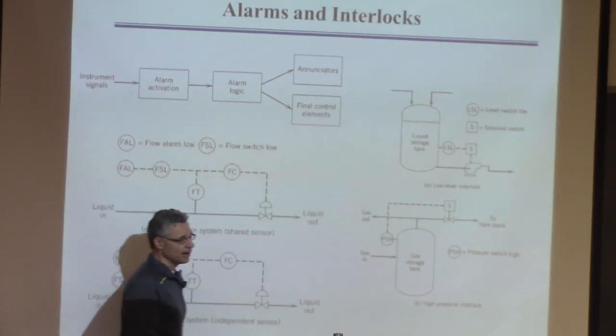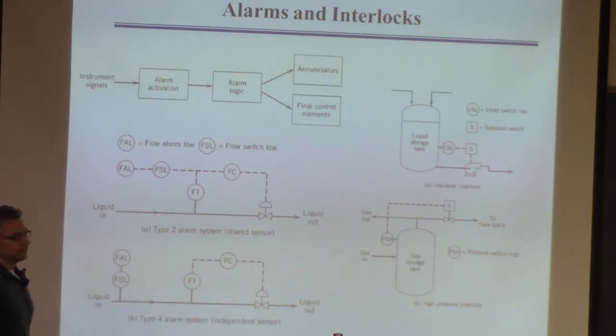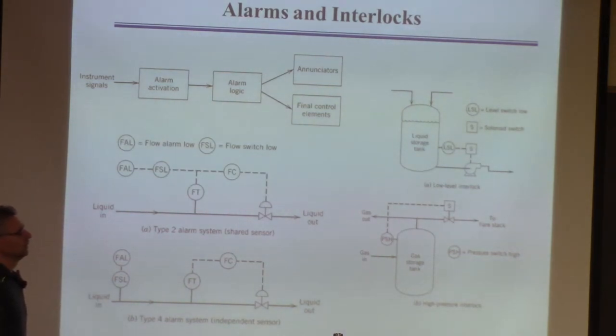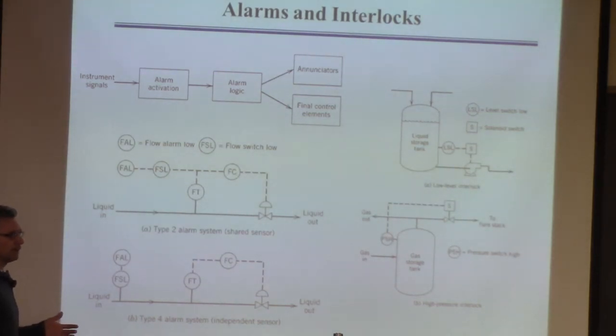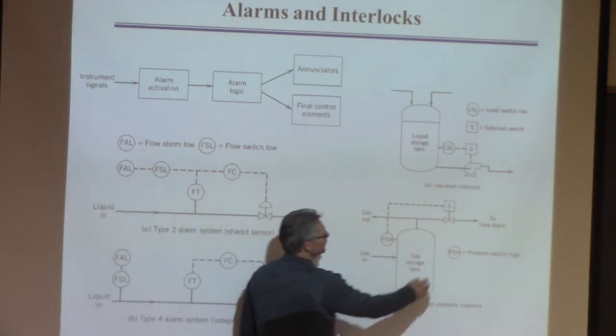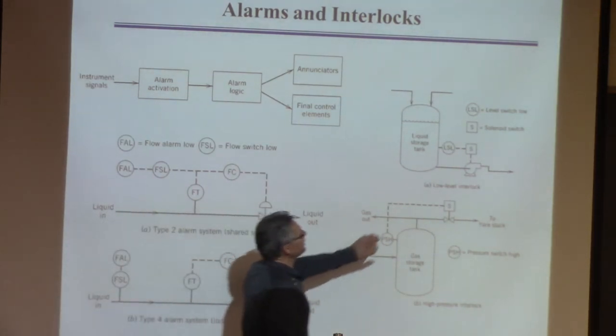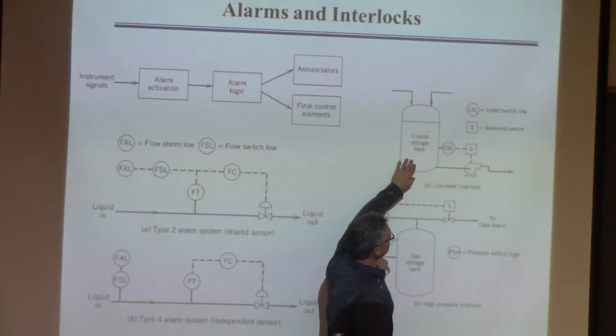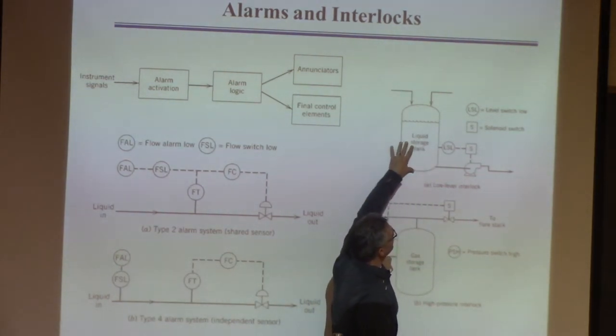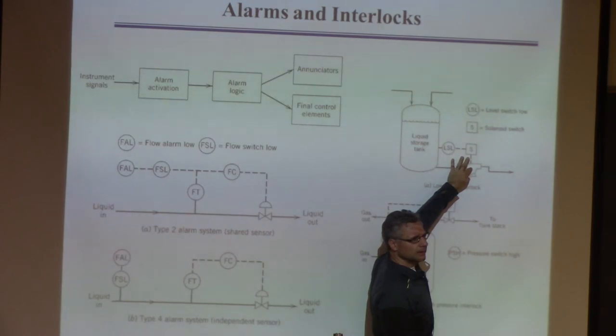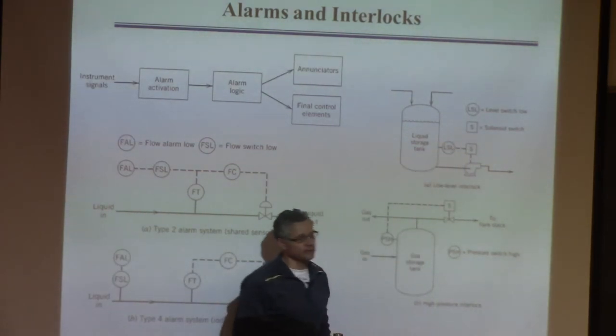Venting will reduce the pressure really quickly. It's not desirable because usually when you vent, you flare — there'll be a fire coming out of the top, and people see that. News crews will go out to a plant and say, why were you flaring from 2 to 3 o'clock on the ethylene unit today? So it's something you don't want to do — it's just for when you have a big problem and have to compensate quickly. Similarly, if the level gets critically high in a tank, you have a solenoid — just an on-off device — that turns a pump on and starts pumping. It's not for regular routine control; it's just for safety purposes.